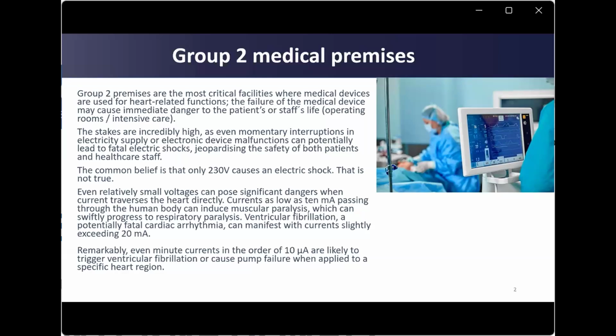Ventricular fibrillation, a potentially fatal cardiac arrhythmia, can manifest with currents slightly exceeding 20 milliamps. Remarkably, even minute currents in the order of 10 microamps have a probability of triggering ventricular fibrillation or causing pump failure when applied directly to the heart.